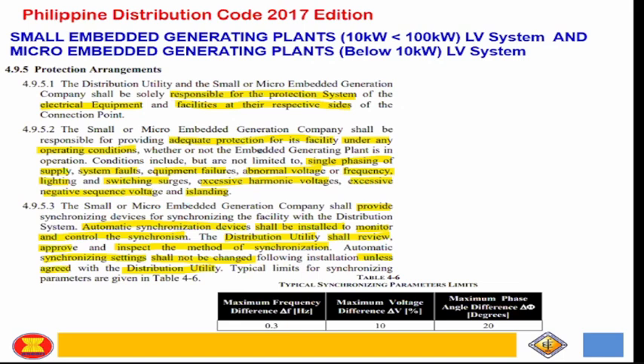So actually, nare-require pa dito yung ano, no? Mayroon talagang synchronism check, or synchronizing system sa side sa LV, yung mga micro and small. And then synchronizing settings, automatic connection settings shall not be changed following the installation unless agreed with the distribution utility.